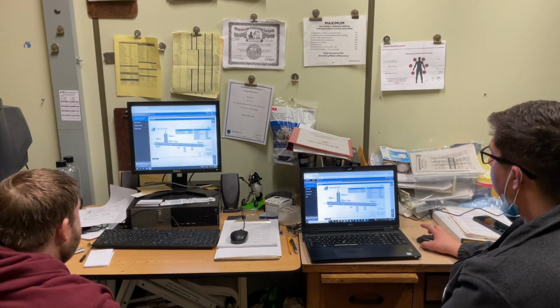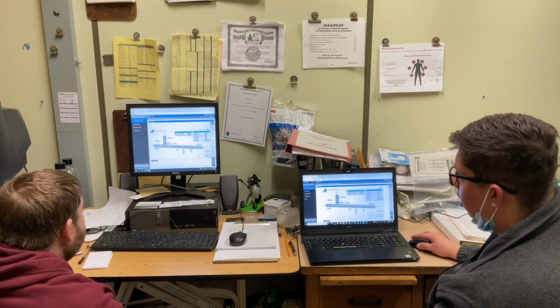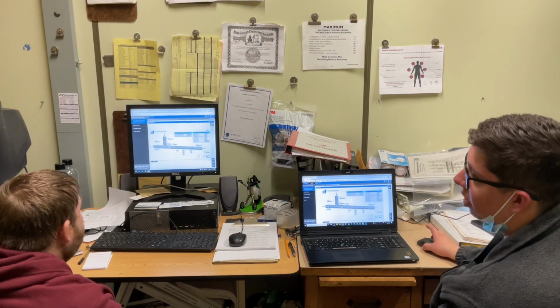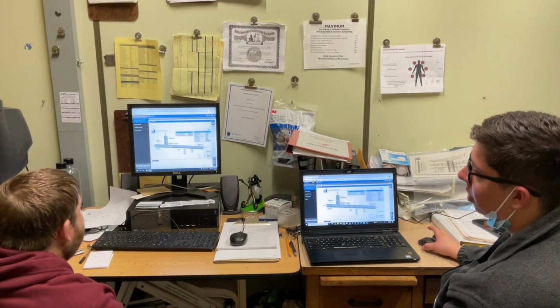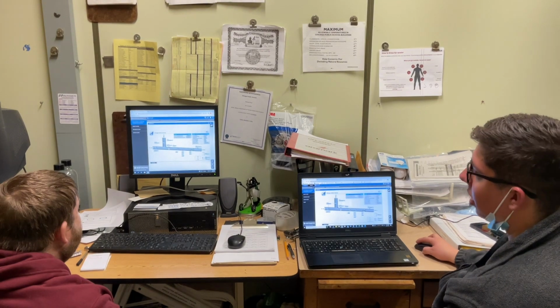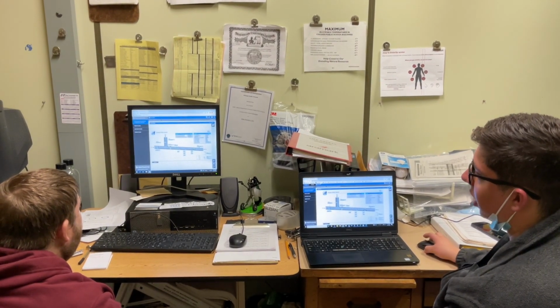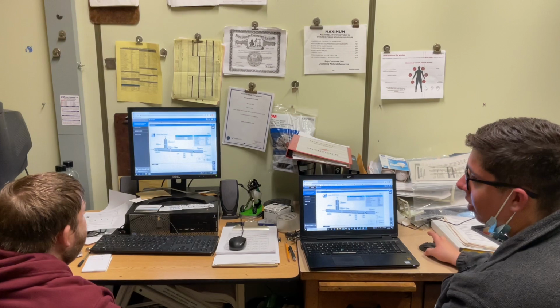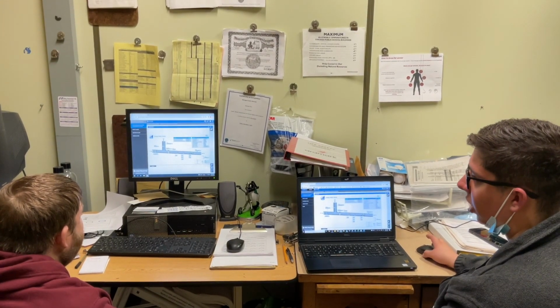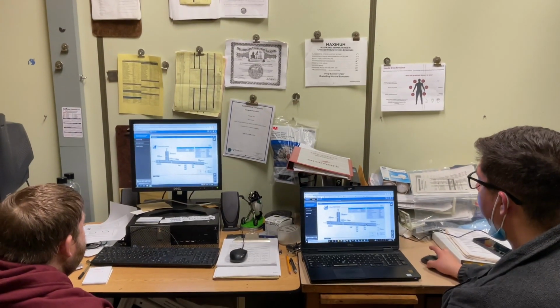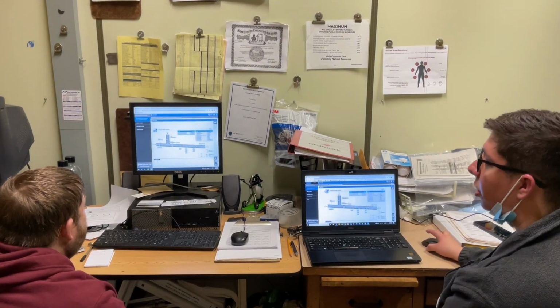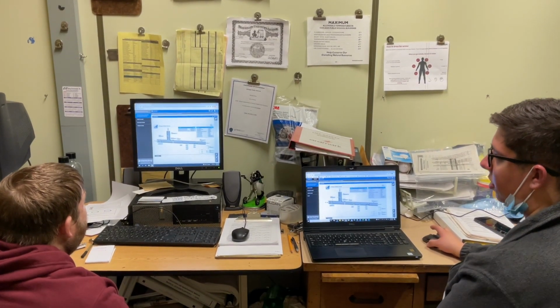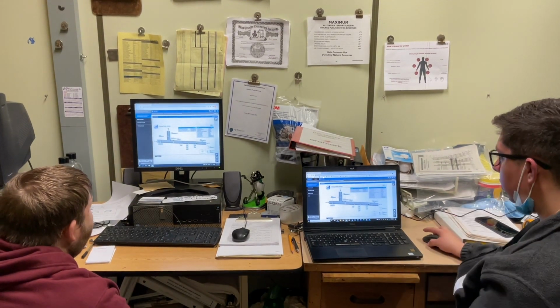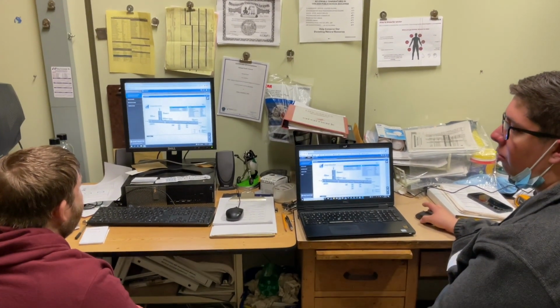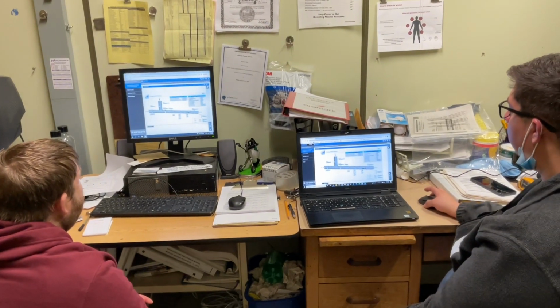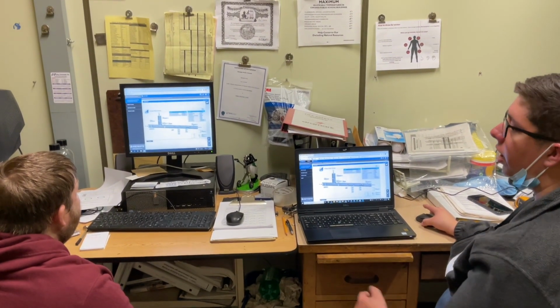Economizer enable, that point up there, is what allows that mixed air damper to open on its own. Right now it's at 71% because economizer is enabled, and it's like, okay, it's 52 degrees out, maybe it needs to cool it off a little bit, so it's going to bring some of that cold air in. If you ever have an issue, you can always turn that false, but that is based on outside air. So there's a reset, it just shuts off on its own. If the outside air gets below, I believe, 50 degrees, then it'll just disable it.